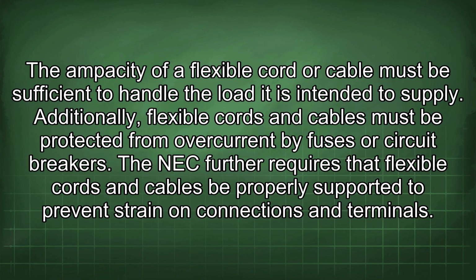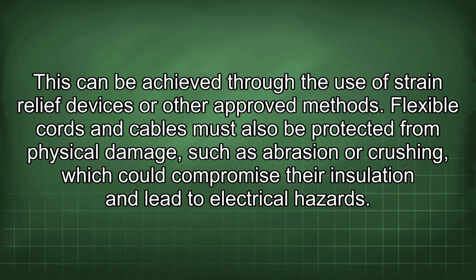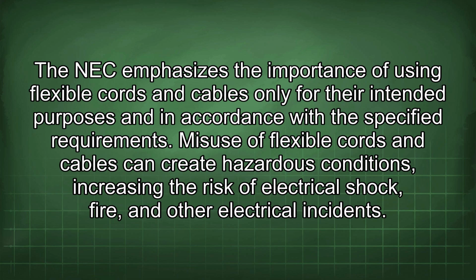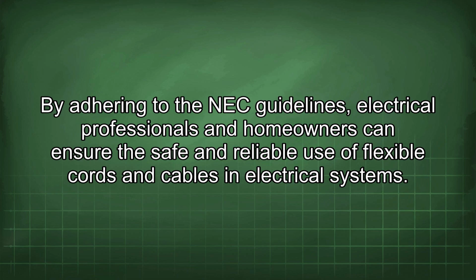The NEC further requires that flexible cords and cables be properly supported to prevent strain on connections and terminals. This can be achieved through the use of strain relief devices or other approved methods. Flexible cords and cables must also be protected from physical damage, such as abrasion or crushing, which could compromise their insulation and lead to electrical hazards. The NEC emphasizes the importance of using flexible cords and cables only for their intended purposes and in accordance with the specified requirements. Misuse of flexible cords and cables can create hazardous conditions, increasing the risk of electrical shock, fire, and other electrical incidents. By adhering to the NEC guidelines, electrical professionals and homeowners can ensure the safe and reliable use of flexible cords and cables in electrical systems.